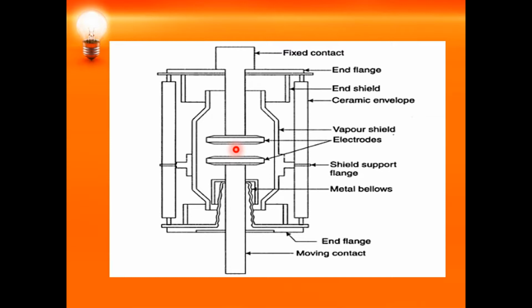So what are the advantages of the vacuum circuit breaker? When compared to oil circuit breakers, it need not be refilled; periodic refilling is not required for vacuum circuit breakers. One thing I have already told you: it will rapidly regain the dielectric strength compared to other circuit breakers, which means less arcing time. And the breaker unit is compact and self-contained, so it can be installed in any required orientation.